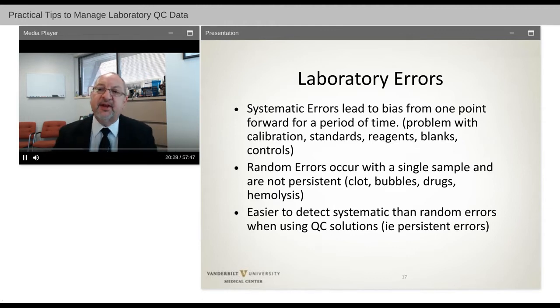Now, systematic errors are easier to detect with quality control because the analyzer performance affects the quality control sample the same way it affects patient samples, with these persistent errors over time, or shifts in performance. However, a random error occurs with one single sample, and that's much harder, or more insidious, to detect with the quality control.